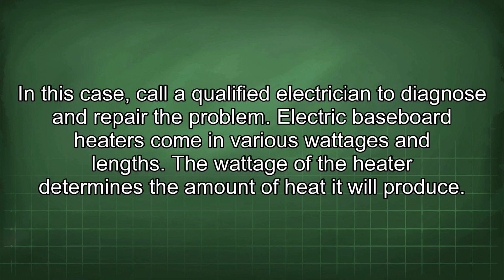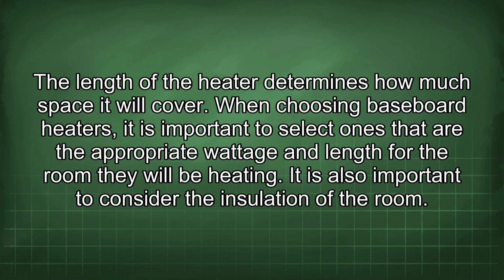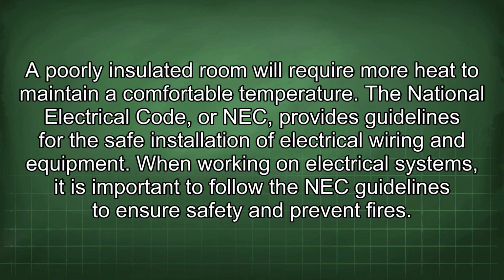Electric baseboard heaters come in various wattages and lengths. The wattage of the heater determines the amount of heat it will produce. The length of the heater determines how much space it will cover. When choosing baseboard heaters, it is important to select ones that are the appropriate wattage and length for the room they will be heating. It is also important to consider the insulation of the room. A poorly insulated room will require more heat to maintain a comfortable temperature.